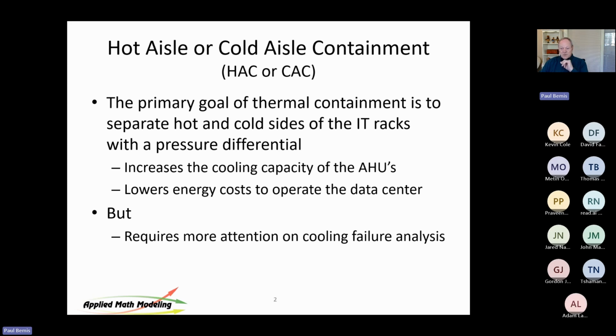And that's the purpose of modeling, is to understand what we call corner cases. Modeling, generally CFD modeling, is generally not about steady state operation. We assume that all of you are smart enough to do the math to figure out you've got enough cooling in the room for your heat load. But what happens during failure analysis, or what happens during high temperature operation? That's really what you use modeling for.